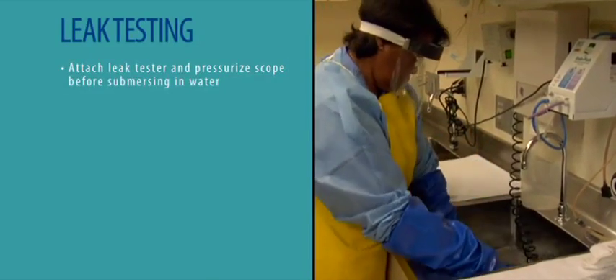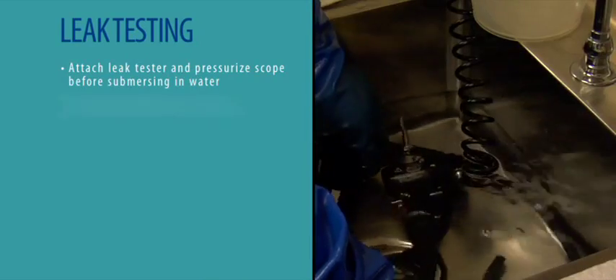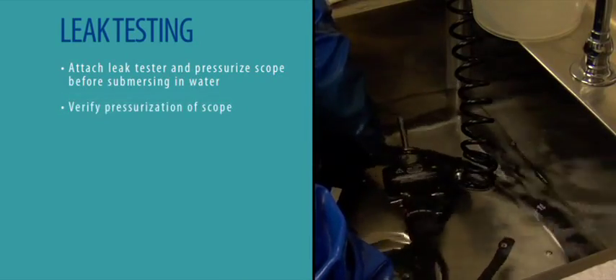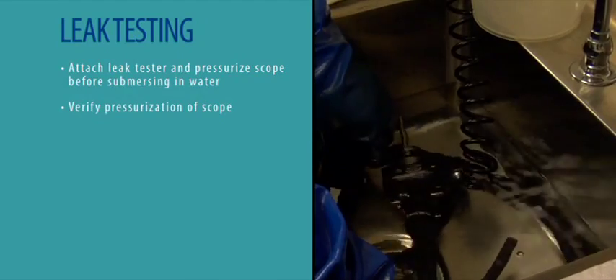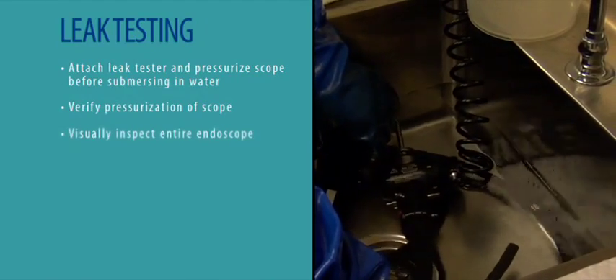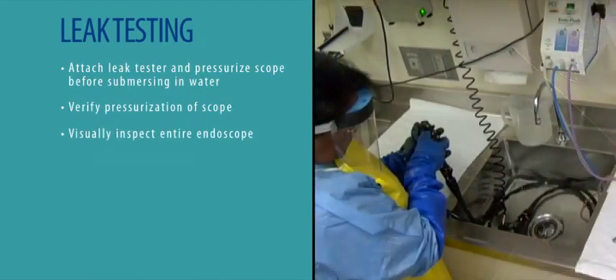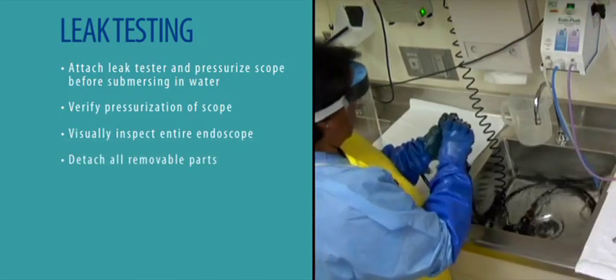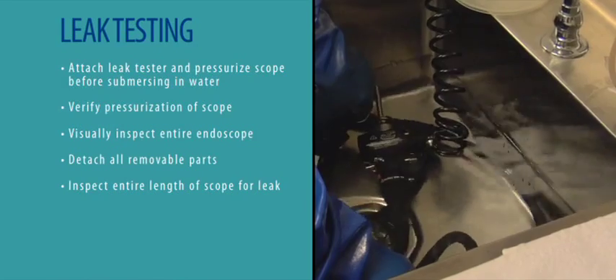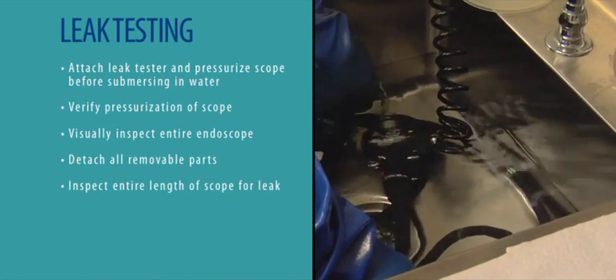Attach the leak tester and pressurize the scope before submersing in water. Verify pressurization of the scope, either visibly or by touch. Visually inspect the entire endoscope for gross damage. Detach all removable parts from the endoscope. With the entire scope submersed, inspect the entire length of the scope for evidence of a leak.